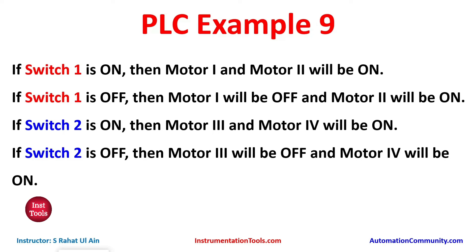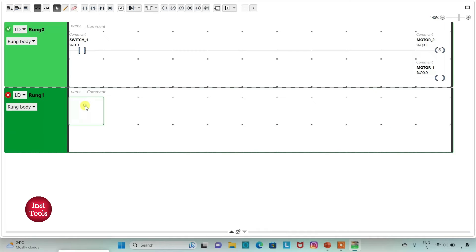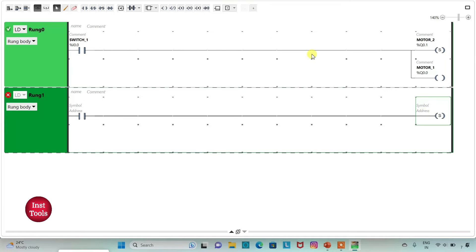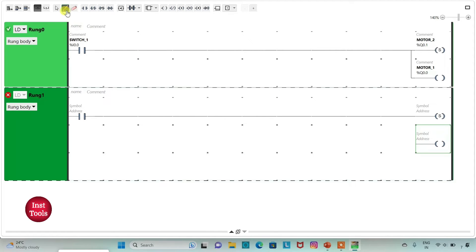Then, if switch 2 is on, motor 3 and motor 4 will be on. If switch 2 is off, motor 3 will be off and motor 4 will be on. We will take motor 4 as a set coil. I will insert a new rung, then insert a normally open contact, one set coil, and another normal coil. I will assign the address to the contact as I 0.1 and add symbol as switch 2.